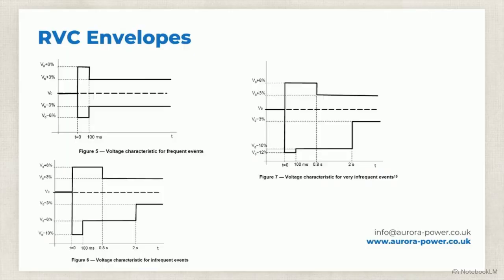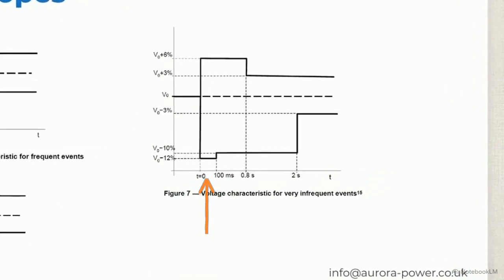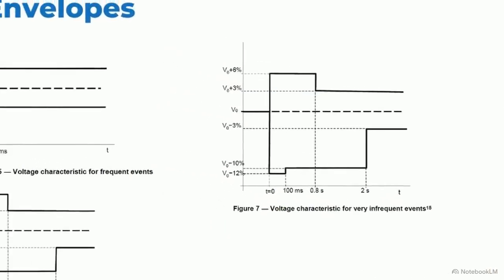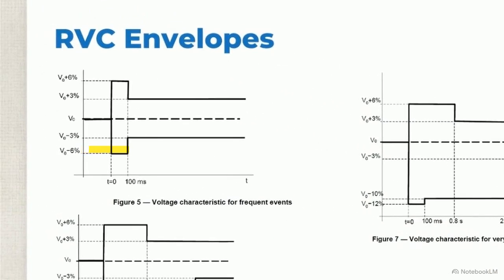These charts detail P28's metric, rapid voltage change, or RVC, setting the allowable severity of voltage dips. The logic: networks tolerate deeper dips only if they are very infrequent. If events happen regularly, the voltage floor is heavily restricted. To prove compliance, developers must model their sites against worst-case assumptions in Section 6.4.2, including minimum fault level. The most critical constraint is Item B, assuming every transformer holds 0.5 per unit of remnant flux before switching.